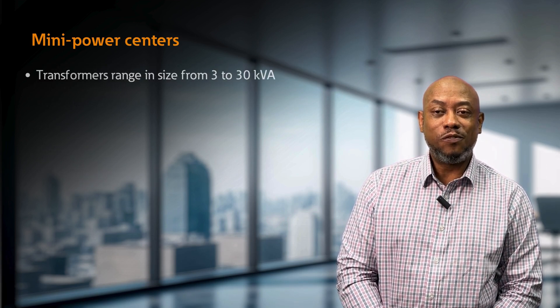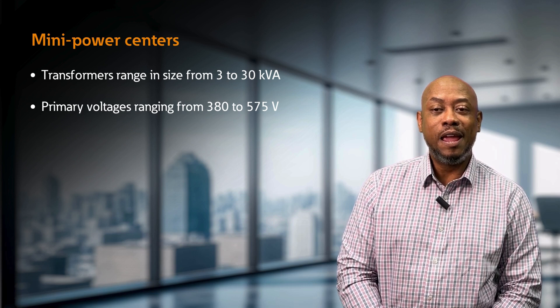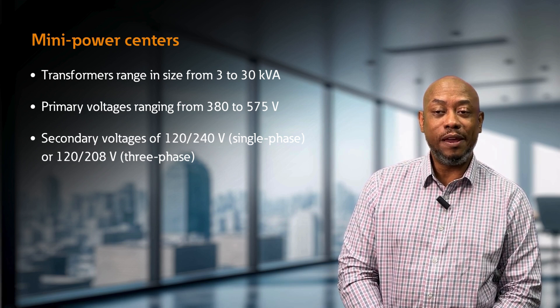Mini power centers transformers range in size from 3 to 30 kVA, with primary voltages ranging from 380 to 575 volts and a secondary voltage of 120 to 240 volts or 120 to 208 volts.